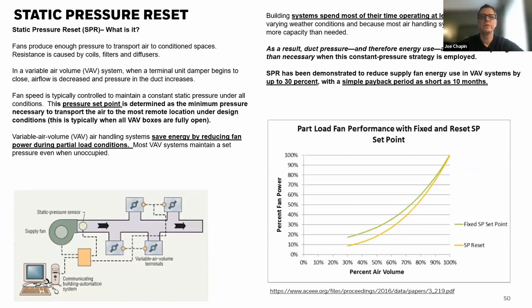The other thing you can do, there's a lot of words on this slide. Let me just put it this way. Static pressure reset. What static pressure reset is, it's determining the amount of air pressure needed to get to the end of the system, the furthest point, to make the system work properly. A lot of times, the static pressure in a building is set higher than it needs to be. And so if you put pressure sensors in place, this will recalculate the amount of static pressure needed to get your system optimally set.